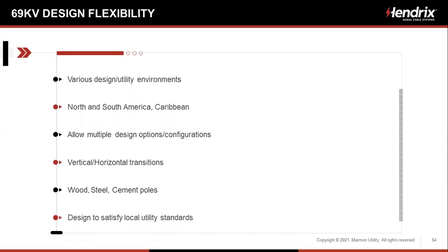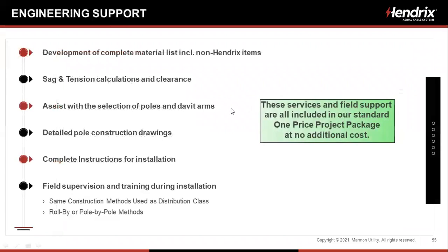We're using every kind of pole we've got on the planet, and we're able to design it to satisfy local standards. Our engineering support includes development of the complete material list, including non-Hendrix items. We do the sag and tension calculations and the clearance calculations. We can either select for you or assist with the selections of poles and davit arms. We have complete detailed pole construction drawings, complete instruction for installation, and we have field supervision and training during installation.